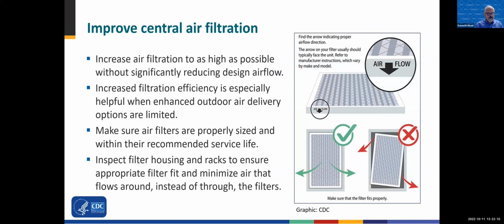Increasing air filtration to as high as possible without significantly reducing design airflow is another intervention. Increased filtration efficiency is especially helpful if it's more difficult to increase your outdoor air. The point being, if I'm cleaning my air with a filter, then perhaps my reliance on needing to open windows becomes less because that filter is doing the work for me, and vice versa. If you go that route, though, inspect the filter housing racks and make sure of the appropriate filter fit, and minimize the chance that air might bypass the filter, and that's what's shown in the little graphic on the right.